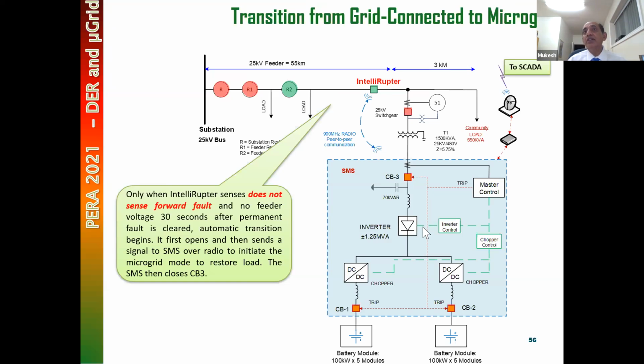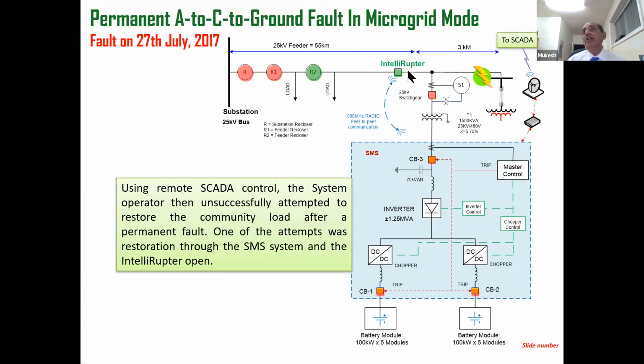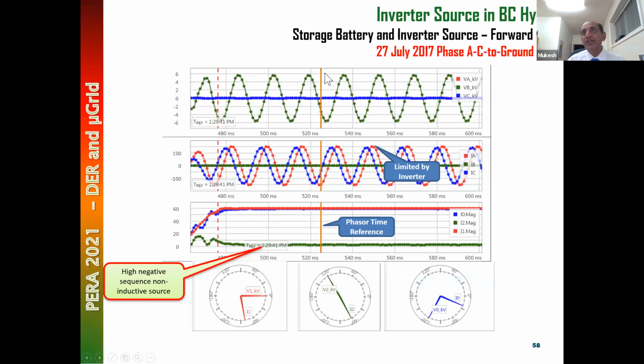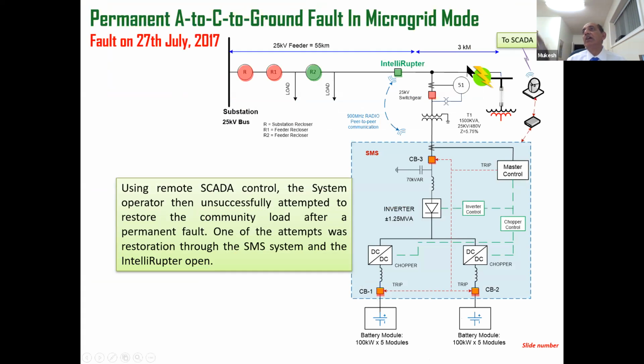If there's a fault here, this recloser will open because it is closest to the fault. It sees a forward fault current. It sees a forward fault current, so this one does nothing. Because of a forward fault current on the grid, there's no point forming a microgrid if this is a permanent fault. It's only if it's a temporary fault that it can do something. So basically, if the forward fault happens, it's not going to do anything. If it's a temporary fault, the recloser will reclose and the supply will be restored.